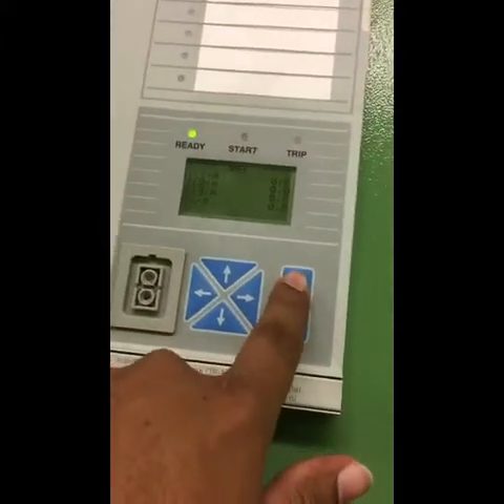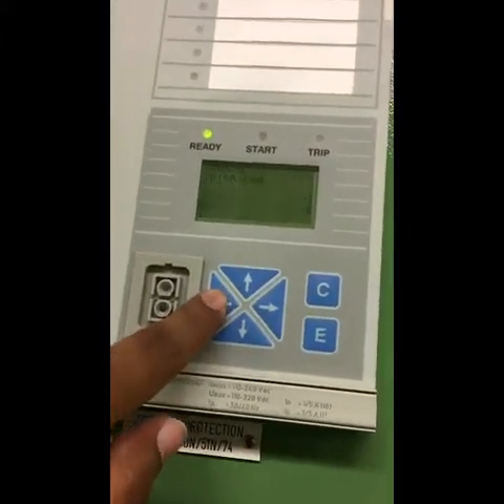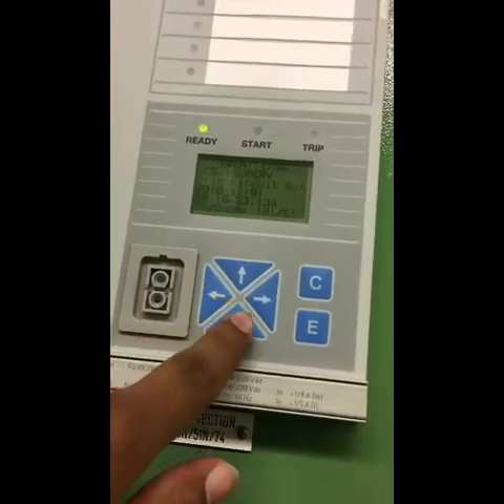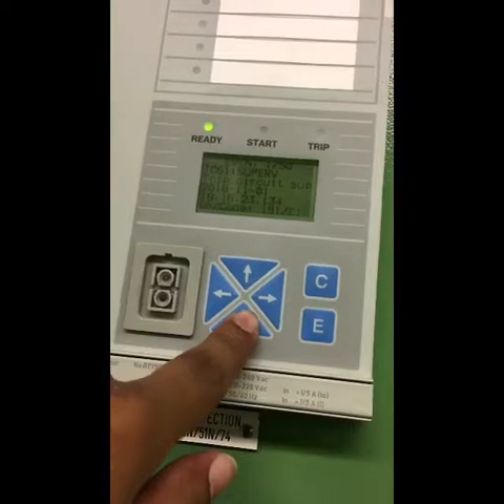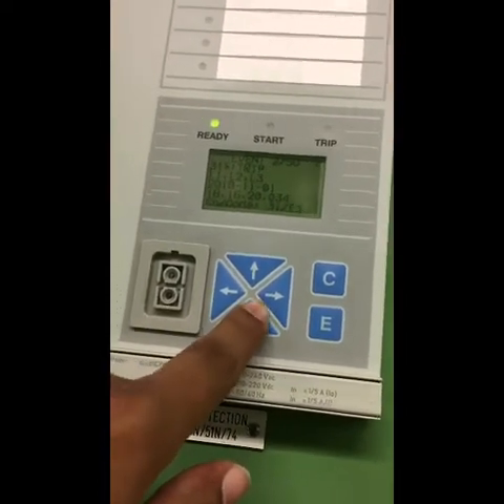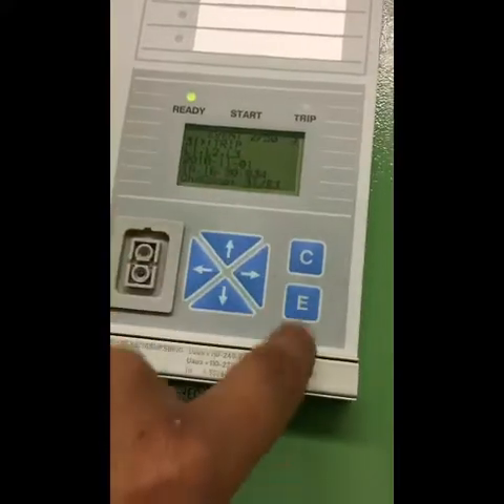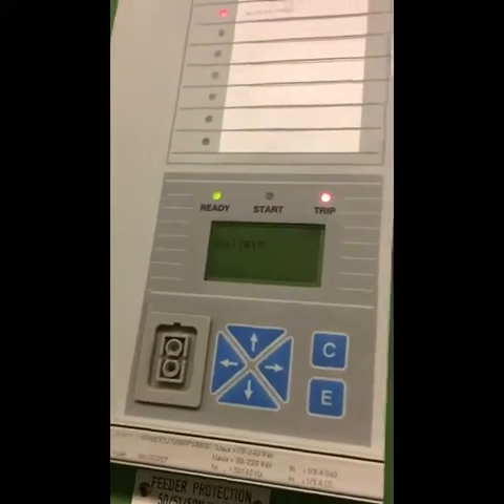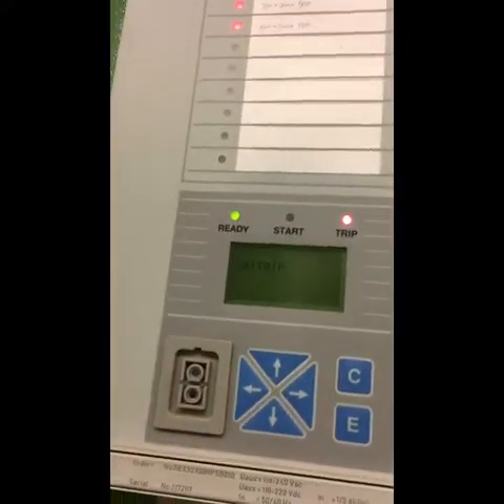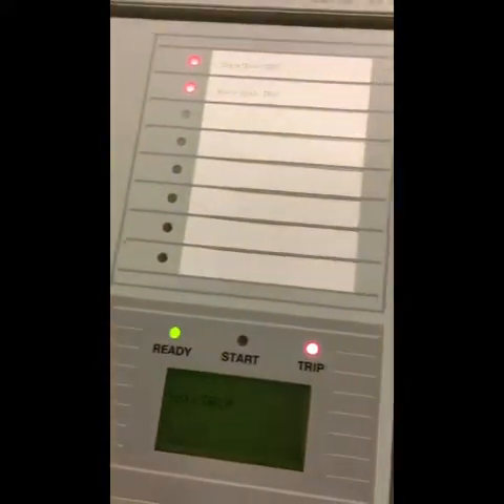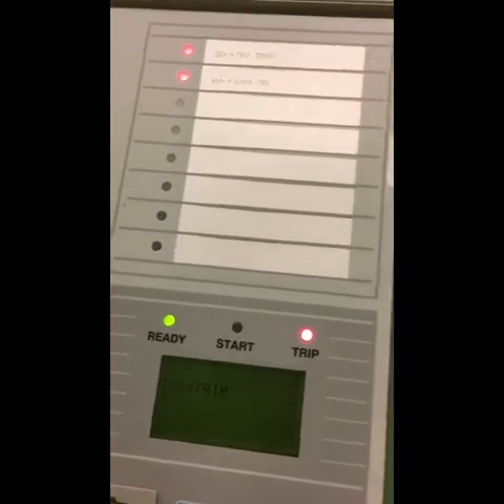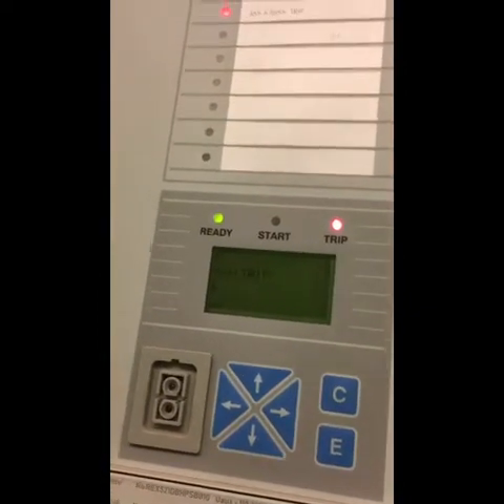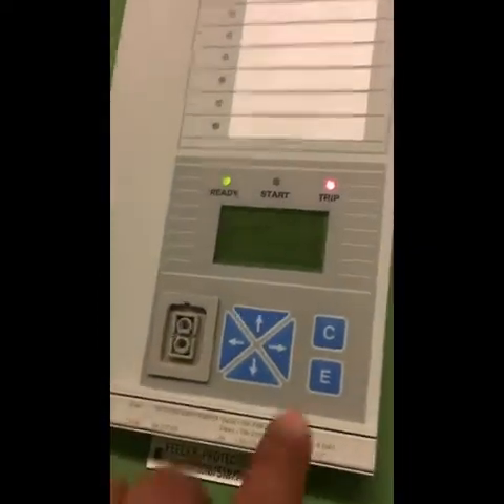First we will reset, and then we go to left arrow, event, trip circuit supervision at 6 o'clock, overcurrent happened on the 3 phases. There is another function here, which is earth fault, and we have earth fault greater. The difference between the two is just a matter of current value and the times. So we have IO greater, meaning overcurrent, earth fault.